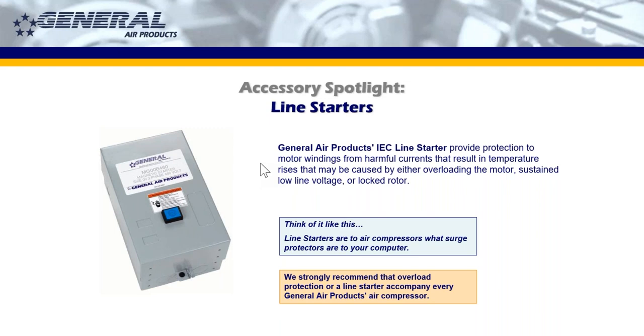When harmful currents hit the motor, you're going to have a temperature rise, and you're going to have the motor overloaded. Alternatively, you can have sustained low voltage that causes overheating of the motor, because the motor is trying to run, but it can't, and that causes overheating as well. And this can be caused by locked rotors as well. We strongly recommend that you use a line starter with any compressor, just to protect the compressor and protect the investment that you made in the compressor. We know that's not always practical, but it doesn't mean it's not a good idea.